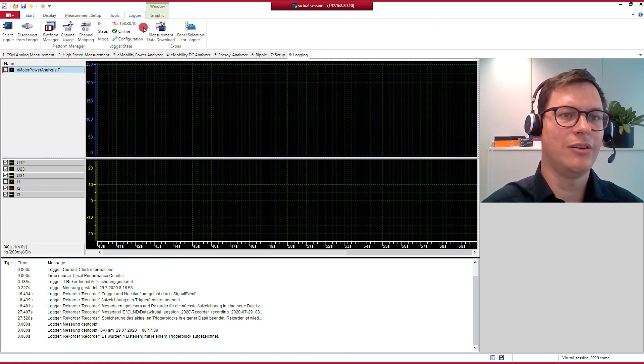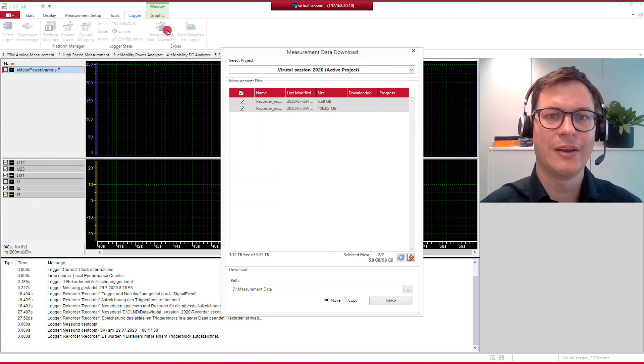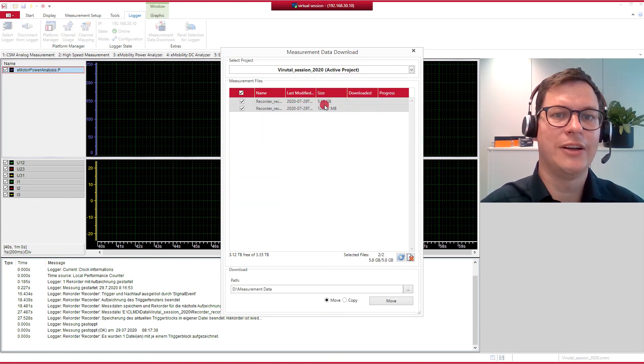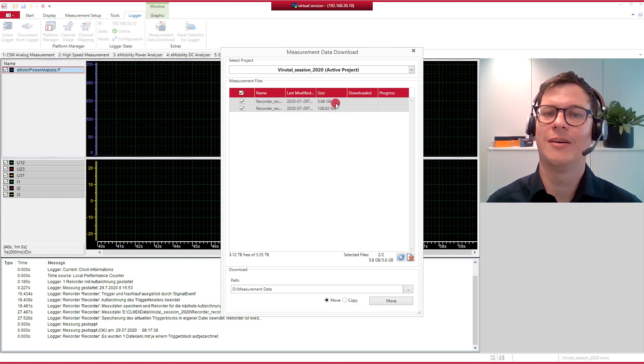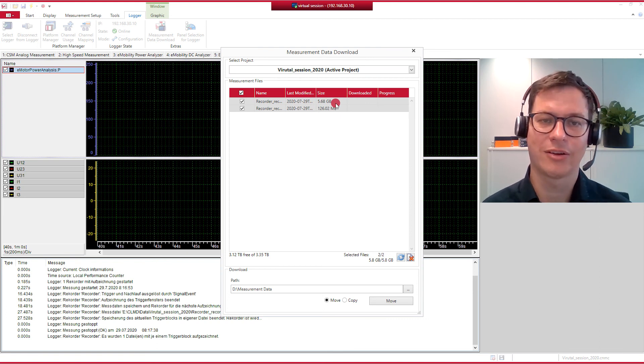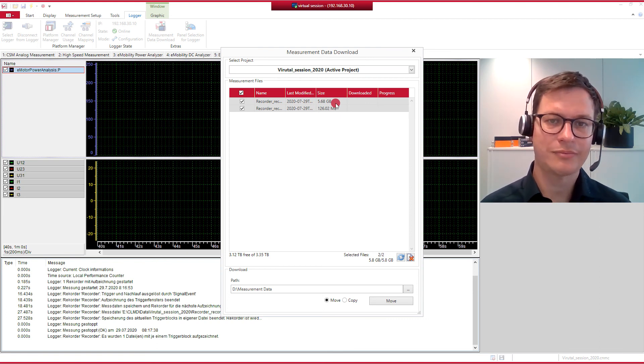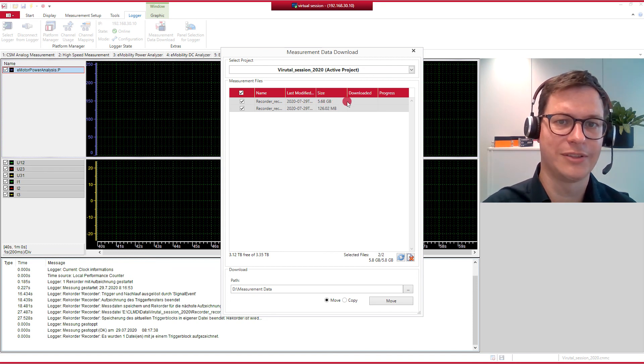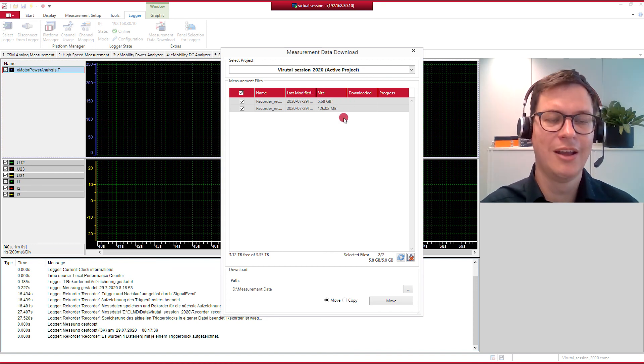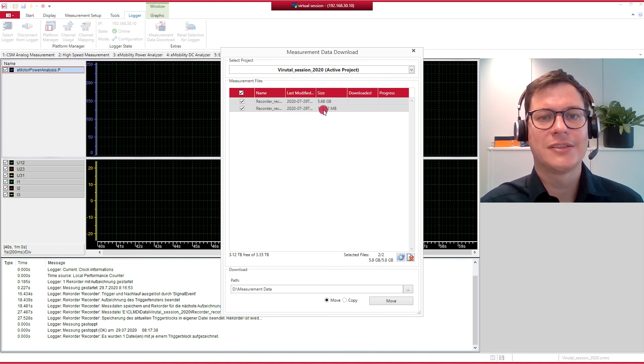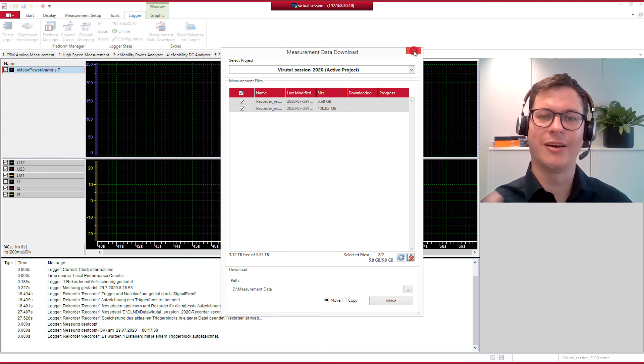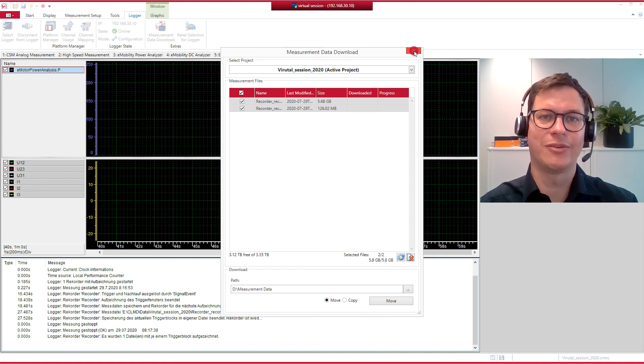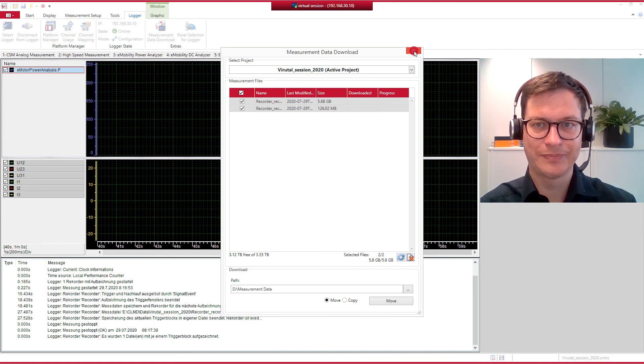So if I stop now, I do expect to find two files on my logger. The one from testing and the second one from the trigger event. So I go to Logger, Measurement Data Download. And I do find two files, the first one already being pretty large, because it was the file where we were checking if all the connections were done properly. And just a few seconds already resulted in a data file of six gigabytes, almost six gigabytes. This one and a half seconds of the trigger, the second one, is already 126 megabytes. So it makes sense to keep the recording time at a reasonable size in order to keep the data files feasible.